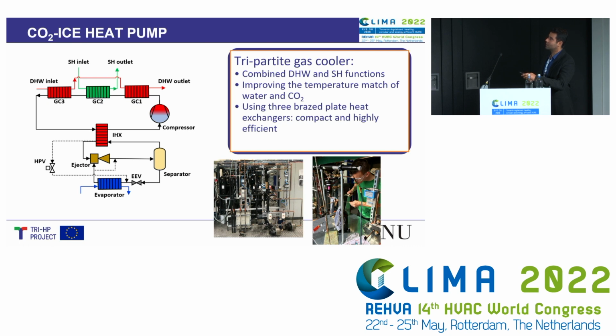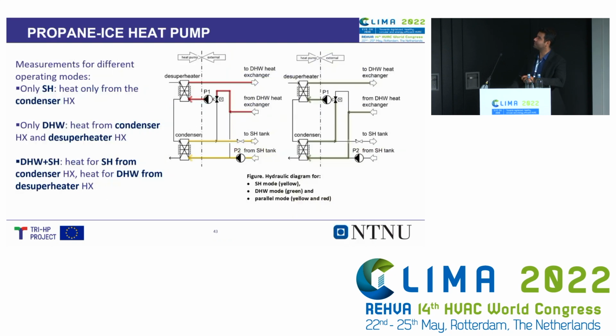For gas cooler 2, we have the space heating inlet and outlet temperatures, which under the design condition are 30 degrees Celsius at the inlet and 35 degrees Celsius at the outlet. So the system is able to work under domestic hot water operation only, space heating only, and also under the combined mode, to have domestic hot water and space heating at the same time. The second prototype is the propane ice heat pump system.